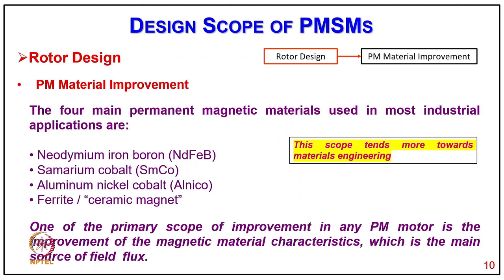The four main permanent magnet materials used in most industry applications are neodymium iron boron, which is considered the best material today, samarium cobalt, which is among the rarest materials, aluminum nickel cobalt, and ferrite also called ceramic magnet. One of the primary scopes of improvement in any PM motor is improving the magnetic material characteristics, which is the main source of field flux.